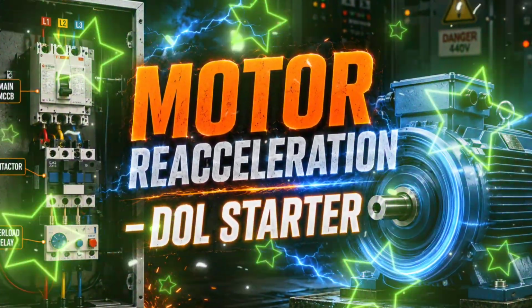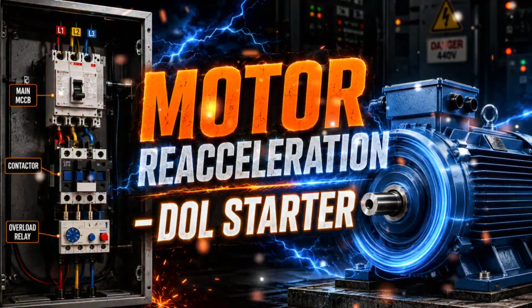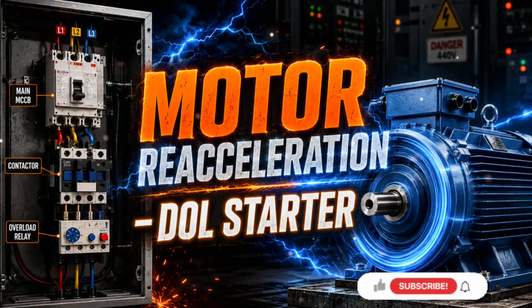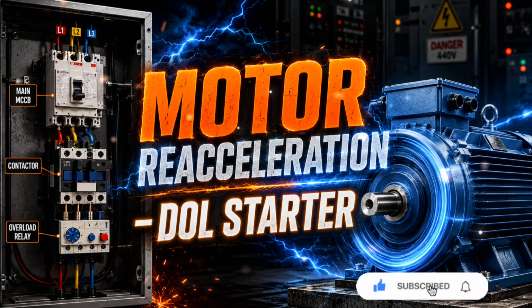Welcome to this technical training on motor reacceleration. In industrial plants like refineries, a momentary voltage dip can cause all motors to trip simultaneously. To prevent a total plant shutdown, we use a reacceleration scheme.